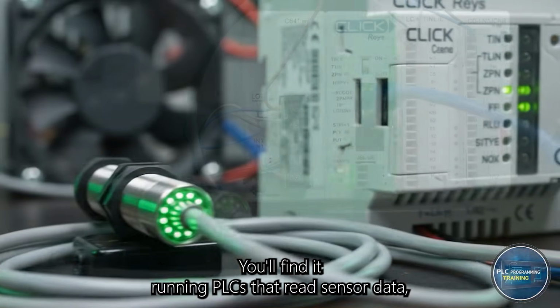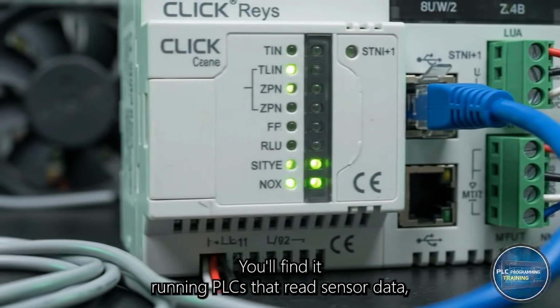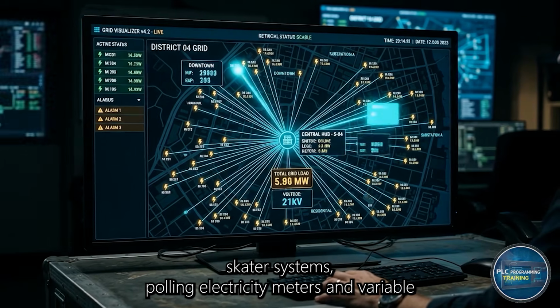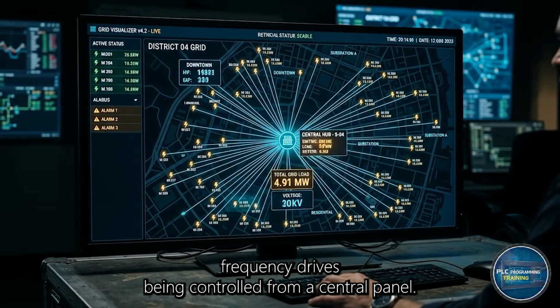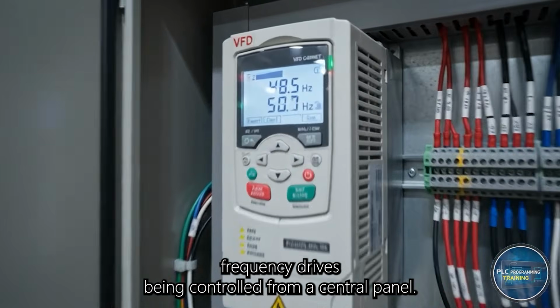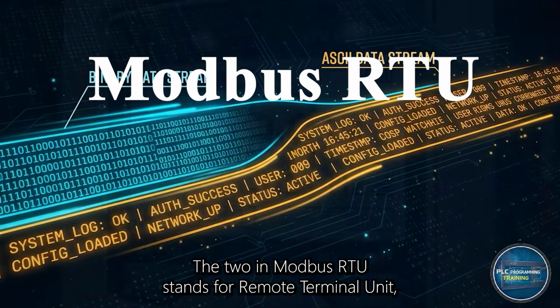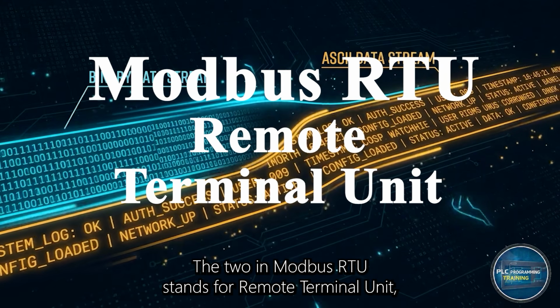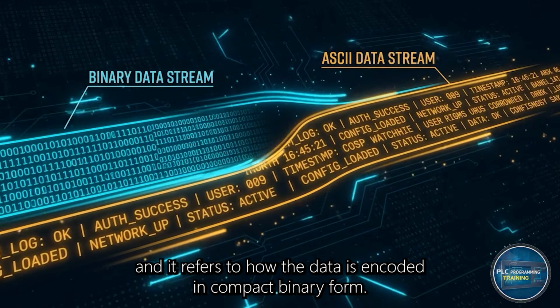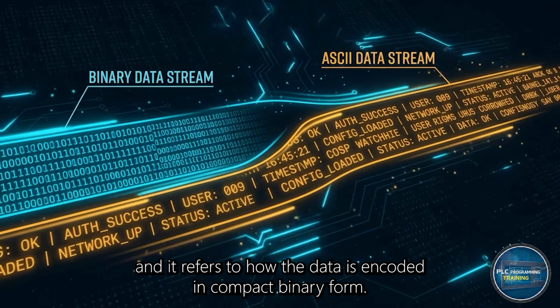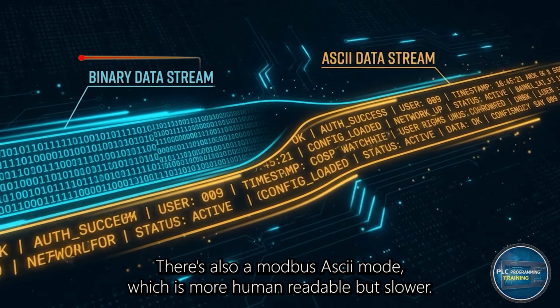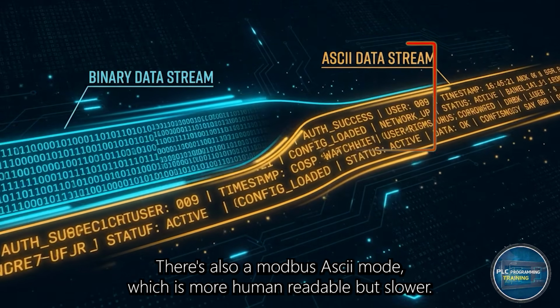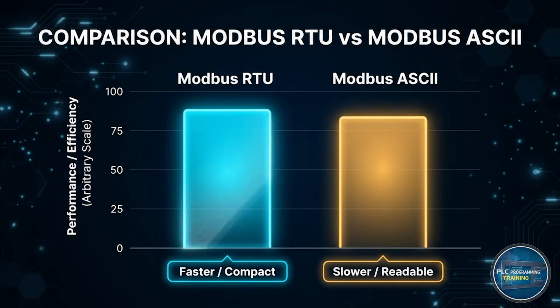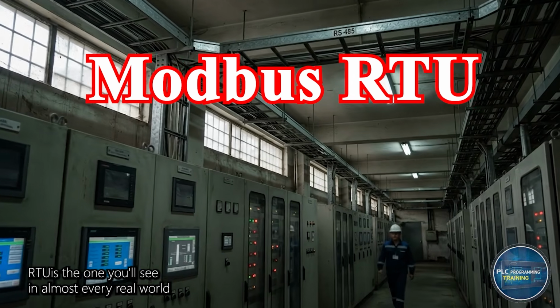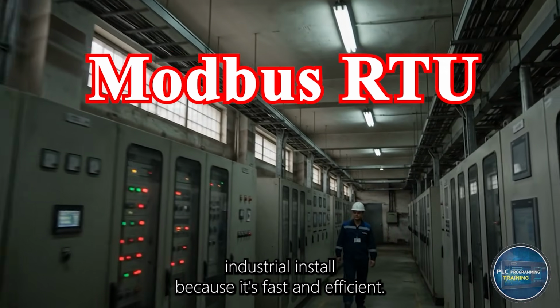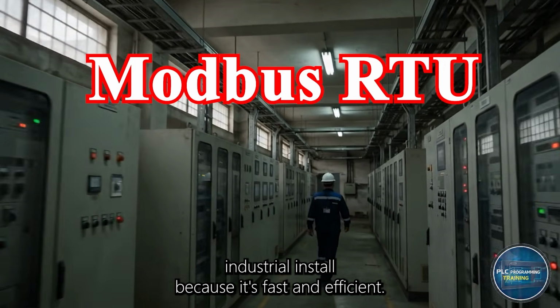You'll find it running PLCs that read sensor data, SCADA systems pulling electricity meters, and variable frequency drives being controlled from a central panel. The RTU in Modbus RTU stands for Remote Terminal Unit, and it refers to how the data is encoded in compact binary form. There's also a Modbus ASCII mode, which is more human-readable but slower. RTU is the one you'll see in almost every real-world industrial install because it's fast and efficient.